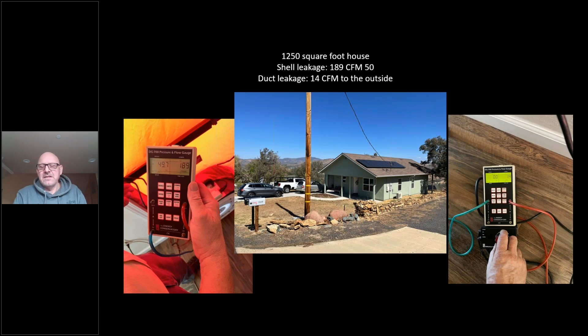So correctly installed HVAC is imperative. I can't tell you how much this means to the performance of your home. You can have the best insulated house and you can have a horribly oversized system. Anything that runs with a compressor, a refrigerator, a gas furnace, a gas water heater, an air conditioner, everything takes 10 to 15 minutes to get to its full running cycle of efficiency. So if your furnace is turning off and on and off and on, it never reaches its state of efficiency. So long run cycles are imperative, especially for a heat pump and especially for air conditioning.